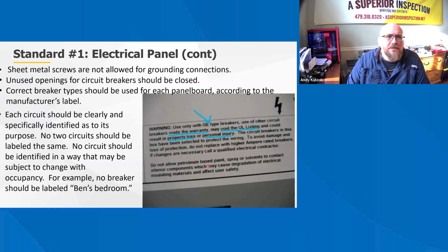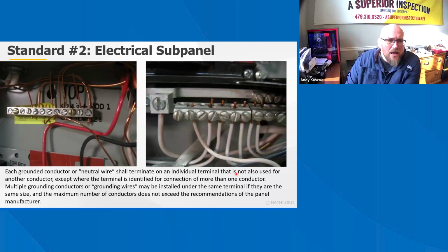On to next, electrical subpanels. Each grounded conductor or neutral wire shall terminate on an individual terminal that is not also used for another conductor, except where the terminal is identified for connection of more than one conductor. Multiple grounding conductors or grounding wires may be installed under the same terminal if they are the same size, and the maximum number of conductors does not exceed the recommendations of the panel manufacturer. In addition, subpanels should be supplied with 4 conductors to isolate grounds and neutrals.